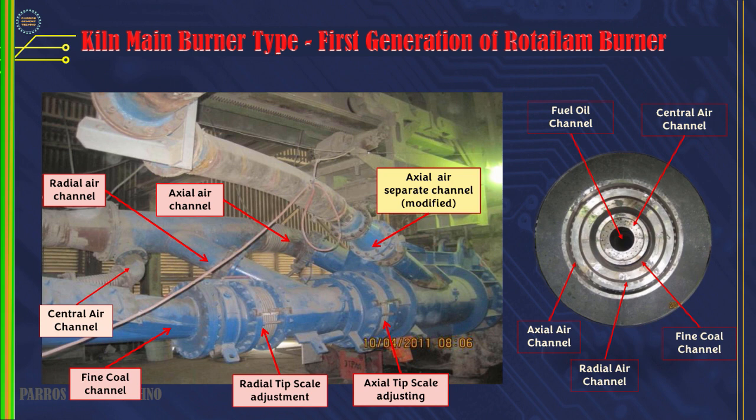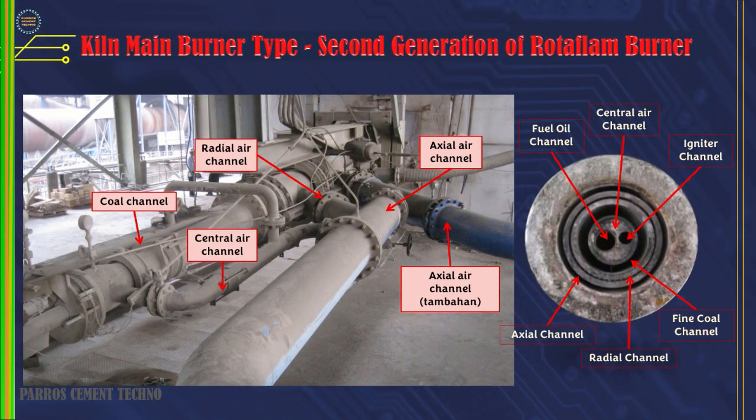With the roots blower addition, the axial primary air pressure can rise to 340 millibar. This is a picture of the second generation Rotaflam burner, which has a larger capacity than the previous type. In this picture there is also an axial auxiliary air duct, because the axial air pressure is only around 178 millibar. After setting the burner nozzle and adding an extra fan, the pressure can rise to 206 millibar.